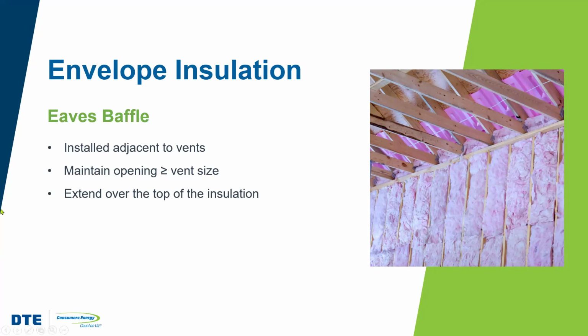The baffle should be continuous even if the soffit venting is not. Right? This helps to ensure that no ventilation air bypasses the baffle. We also want to make sure to seal the bottom edges of the baffle to the top plate in order, again, to prevent any air from bypassing and also to prevent air from leaking into the insulation.